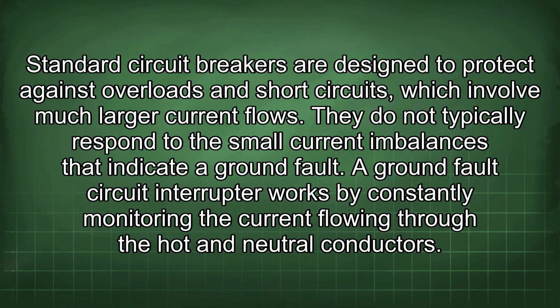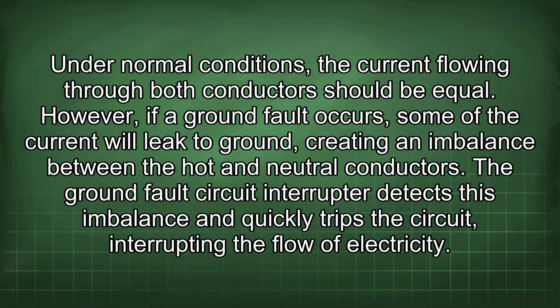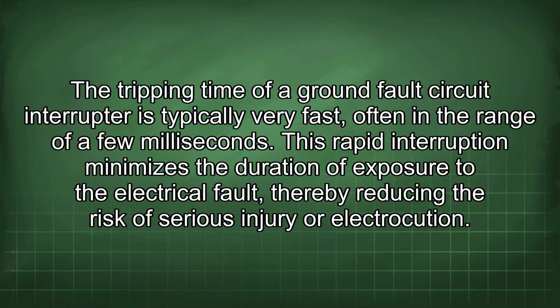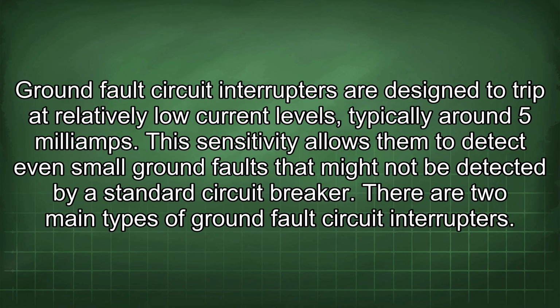A ground fault circuit interrupter works by constantly monitoring the current flowing through the hot and neutral conductors. Under normal conditions, the current flowing through both conductors should be equal. However, if a ground fault occurs, some of the current will leak to ground, creating an imbalance between the hot and neutral conductors. The ground fault circuit interrupter detects this imbalance and quickly trips the circuit, interrupting the flow of electricity. The tripping time of a ground fault circuit interrupter is typically very fast, often in the range of a few milliseconds. This rapid interruption minimizes the duration of exposure to the electrical fault, thereby reducing the risk of serious injury or electrocution. Ground fault circuit interrupters are designed to trip at relatively low current levels, typically around 5 milliamps. This sensitivity allows them to detect even small ground faults that might not be detected by a standard circuit breaker.